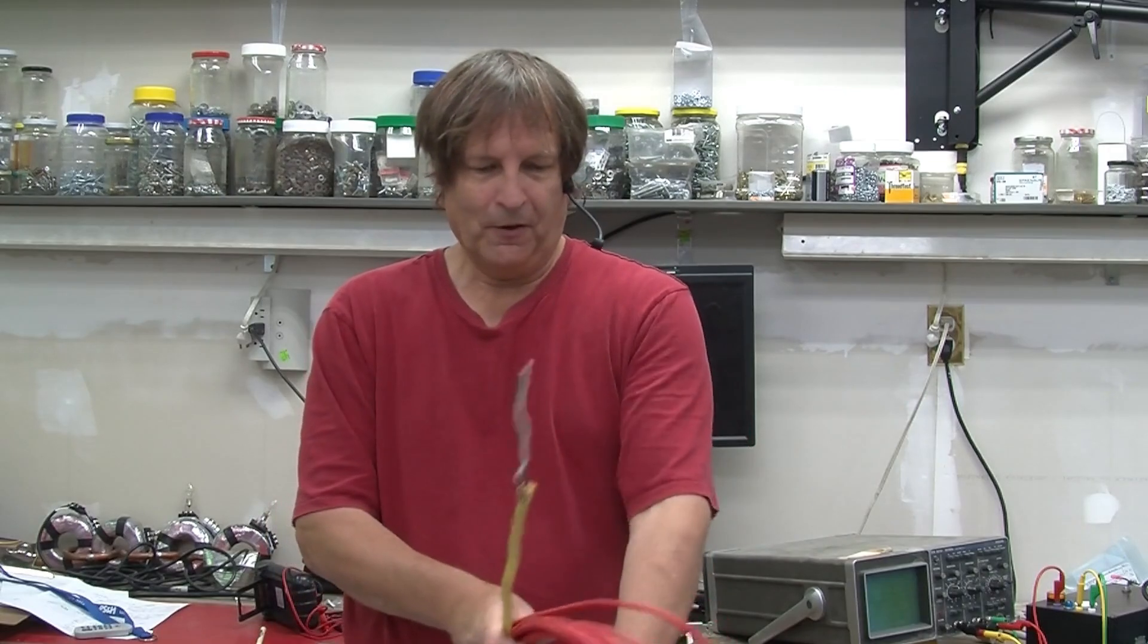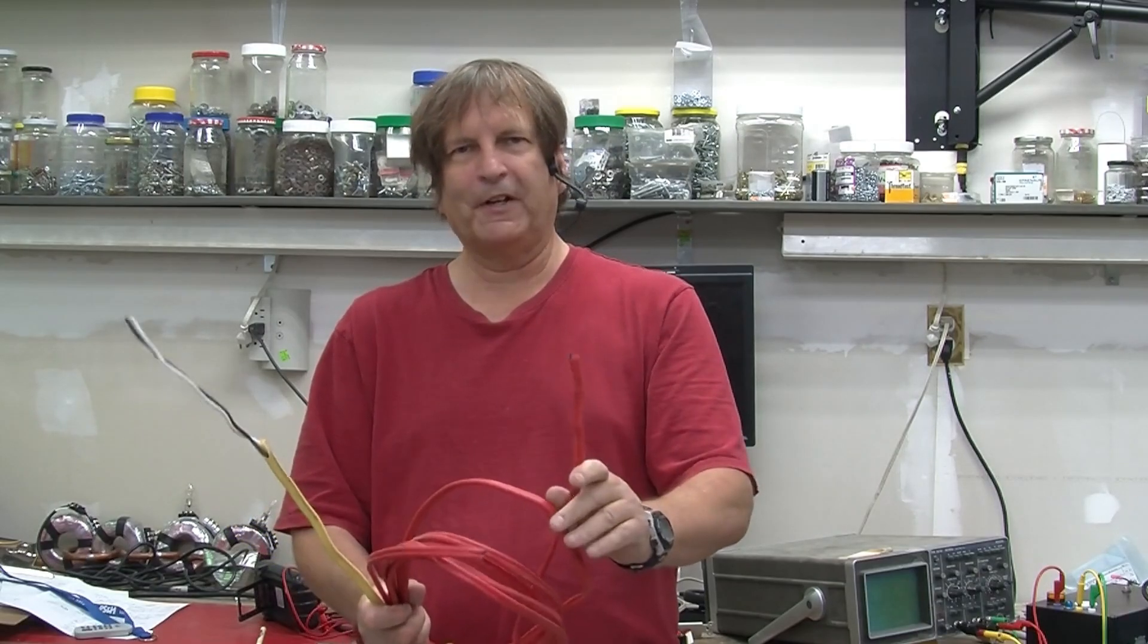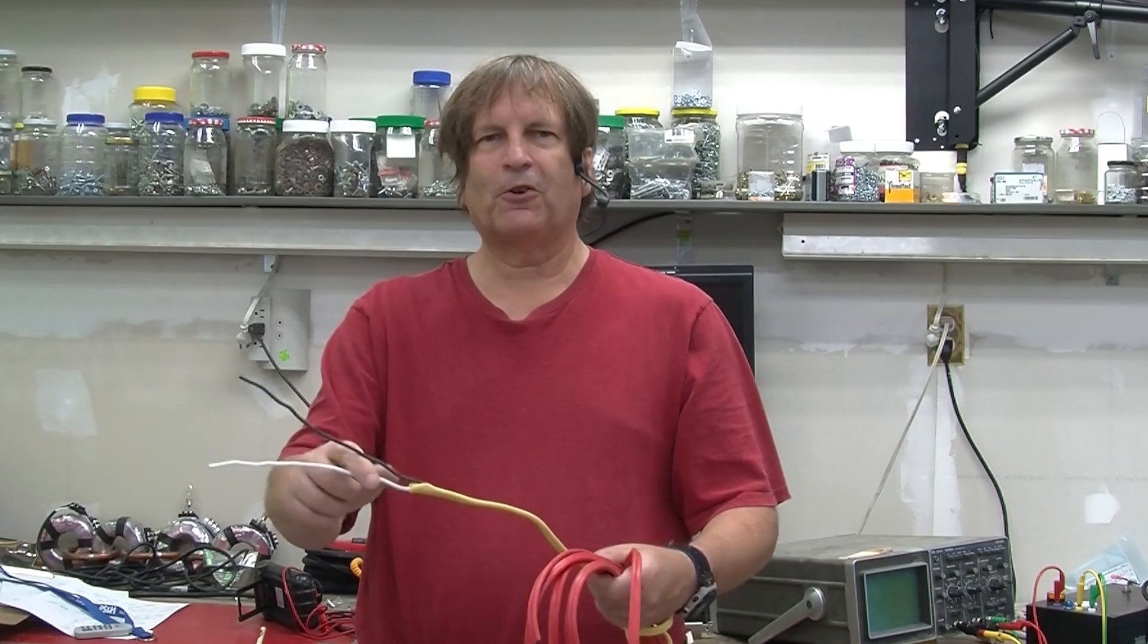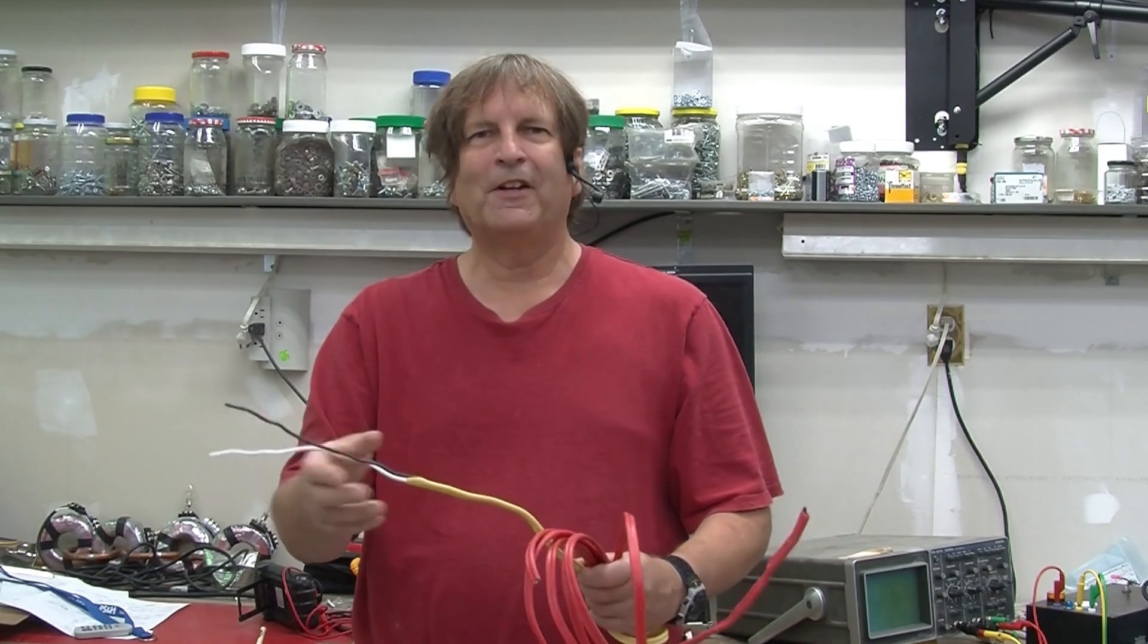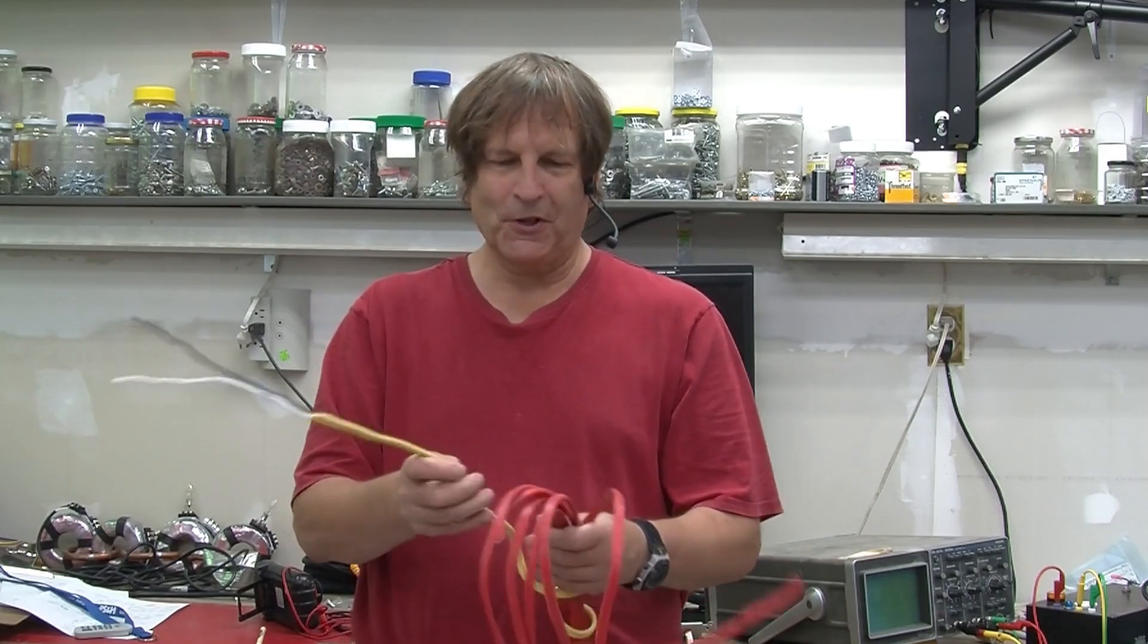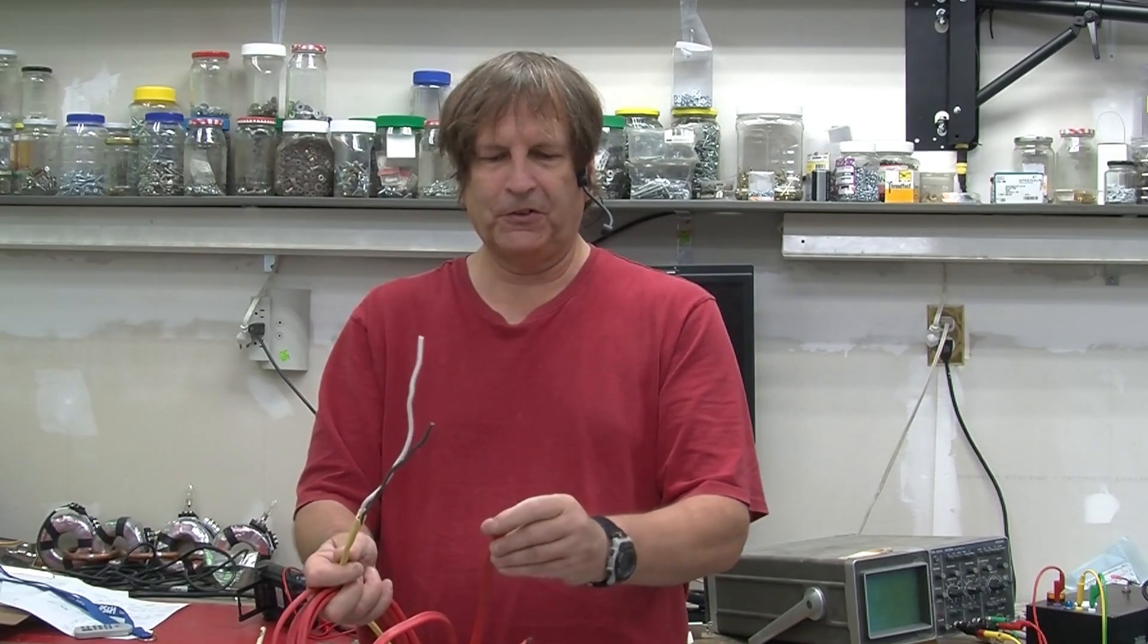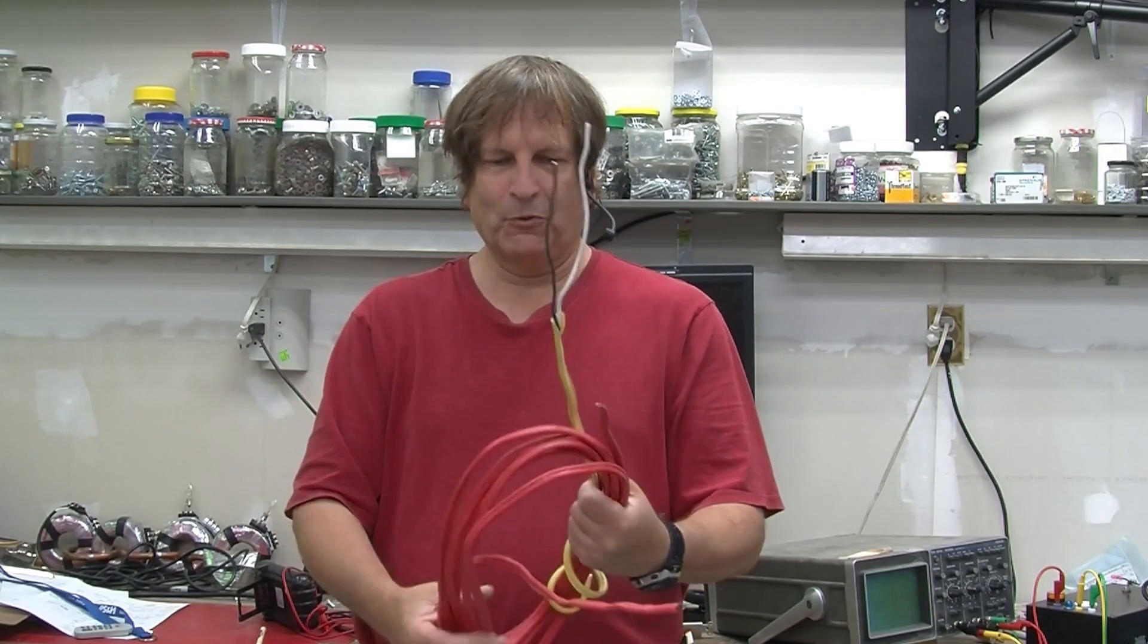Now, if you're still doubting it, over here we have some nice red cable. That is cable that's intended for 240 volt applications. It's number 12 and rated at 20 amps. Over here I have some nice yellow cable. It's intended for 120 volt applications. It is number 12 wire and it's also rated at 20 amps. So both of these cables are intended for different voltage applications or different voltages between the two wires in them, yet they have the same thickness of wire and have the same ampacity rating of 20 amps.